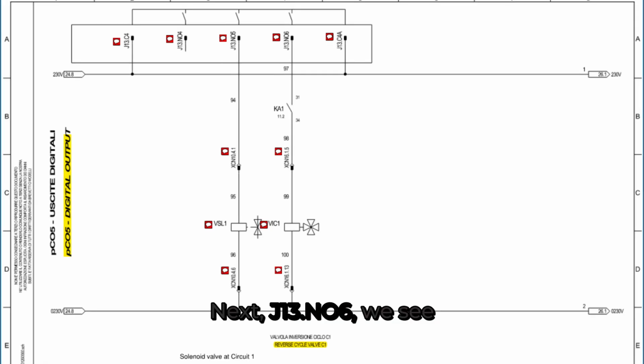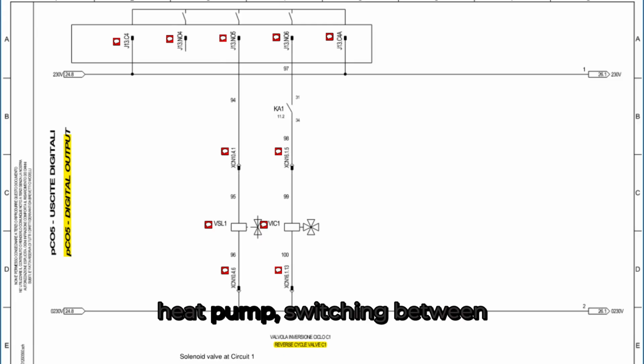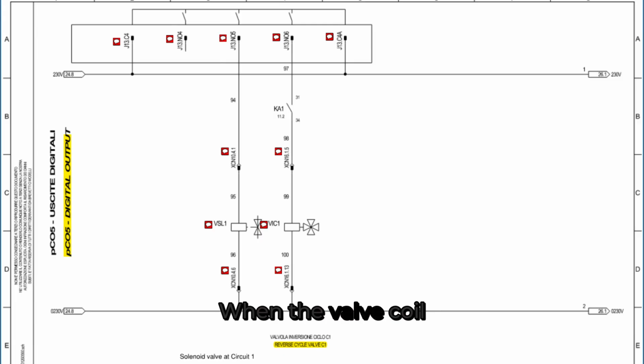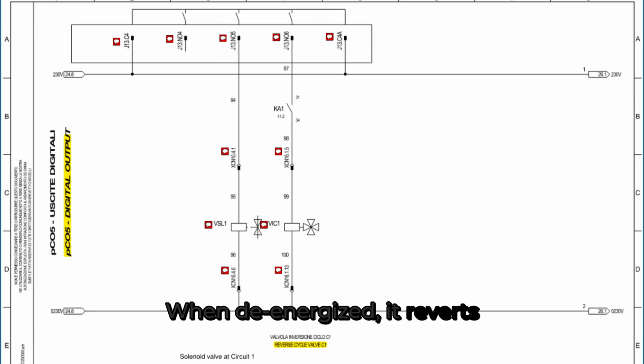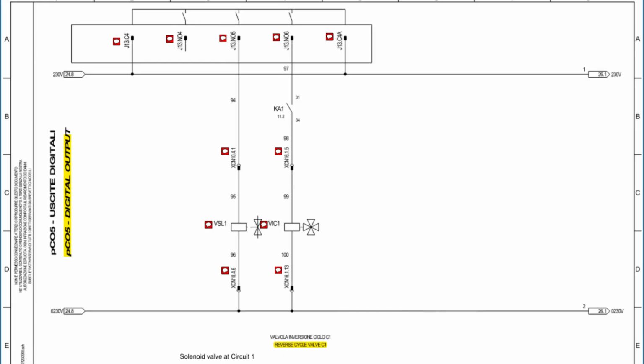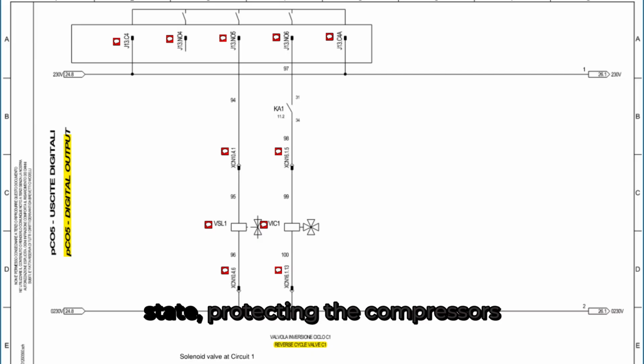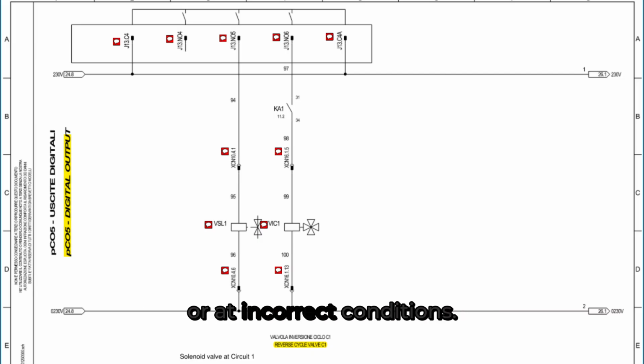Next, at J13.NO6, we see VIC1, labeled as the reverse cycle valve for circuit 1. This valve determines the operational mode of the heat pump, switching between heating and cooling. When the valve coil is energized, it changes the refrigerant flow direction by reversing the high and low sides of the circuit, effectively switching the condenser and evaporator roles. When de-energized, it reverts to its default mode, usually cooling. The reverse cycle valve coil receives power through relay contact KA1, shown in series with the output line. This ensures that the valve can only operate when the system is in the proper control state, protecting the compressors from switching under load or at incorrect conditions.